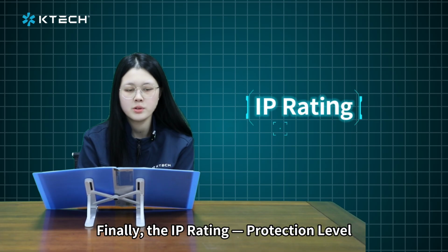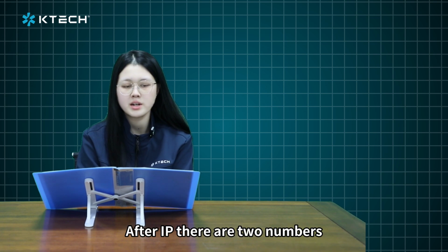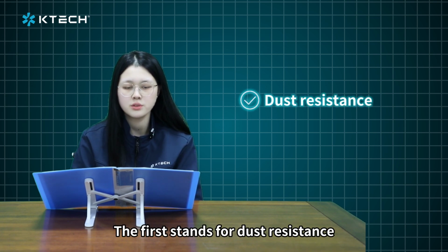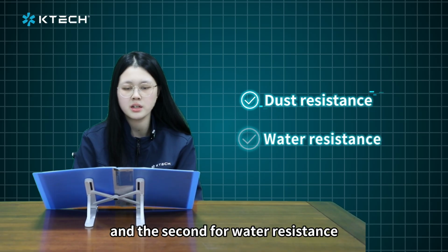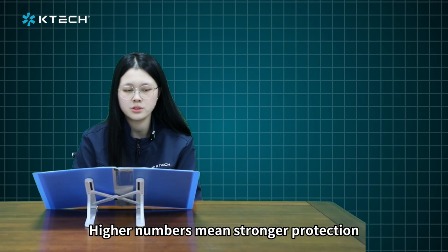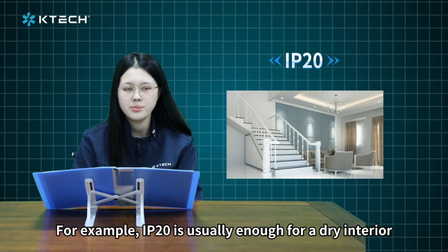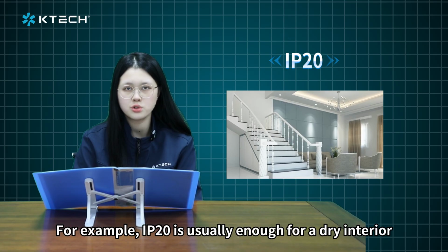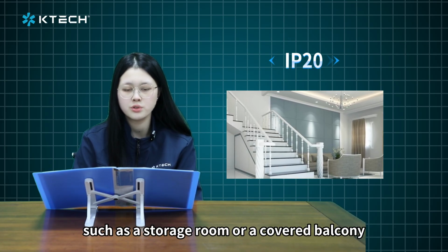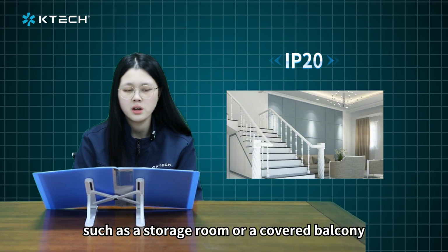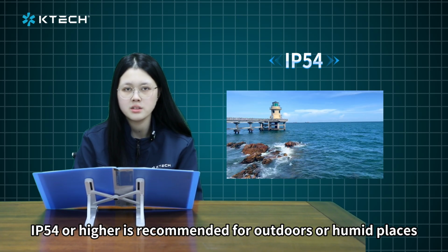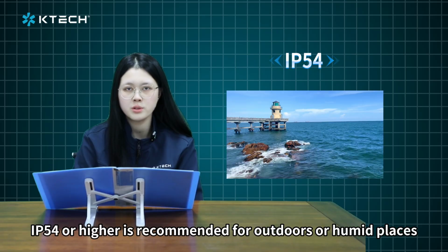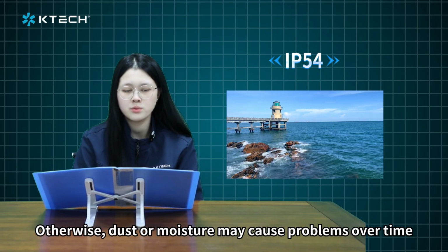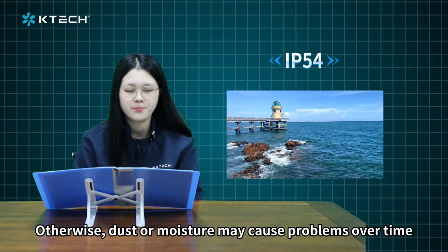Finally, the IP rating, the protection level. After IP, there are two numbers. The first stands for dust resistance and the second for water resistance. Higher number means stronger protection. For example, IP20 is usually enough for a dry interior, such as a storage room or a covered balcony. IP54 or higher is recommended for outdoors or humid places. Otherwise, dust or moisture may cause problems over time.